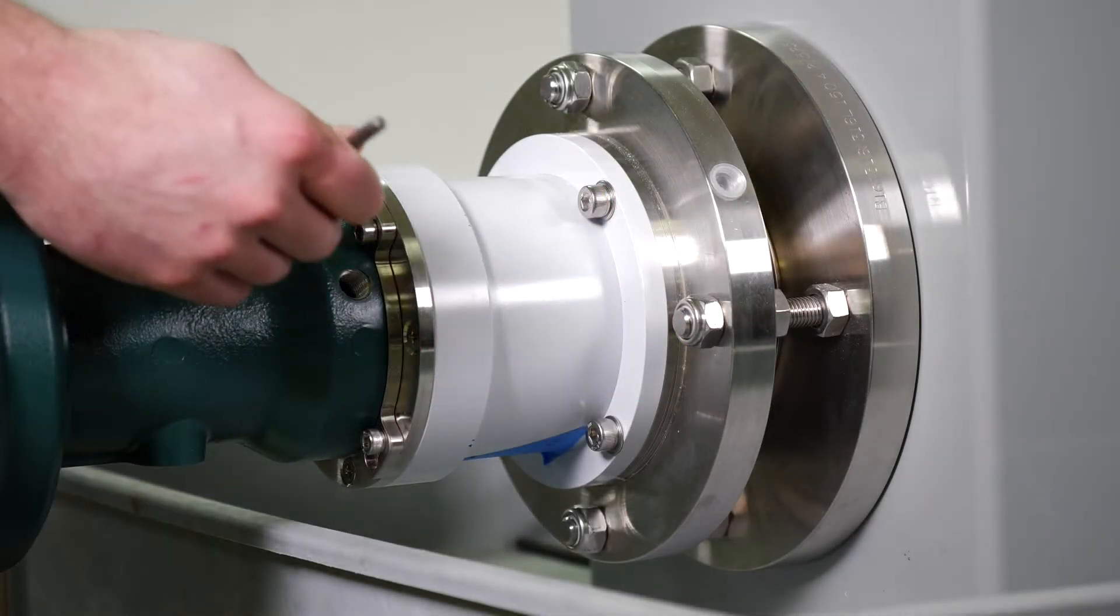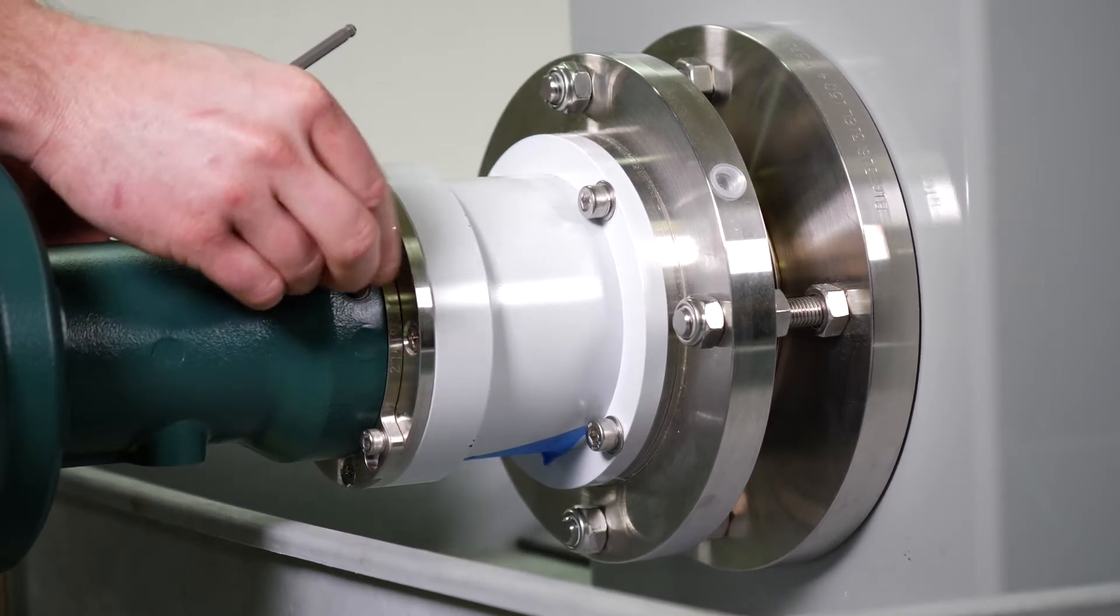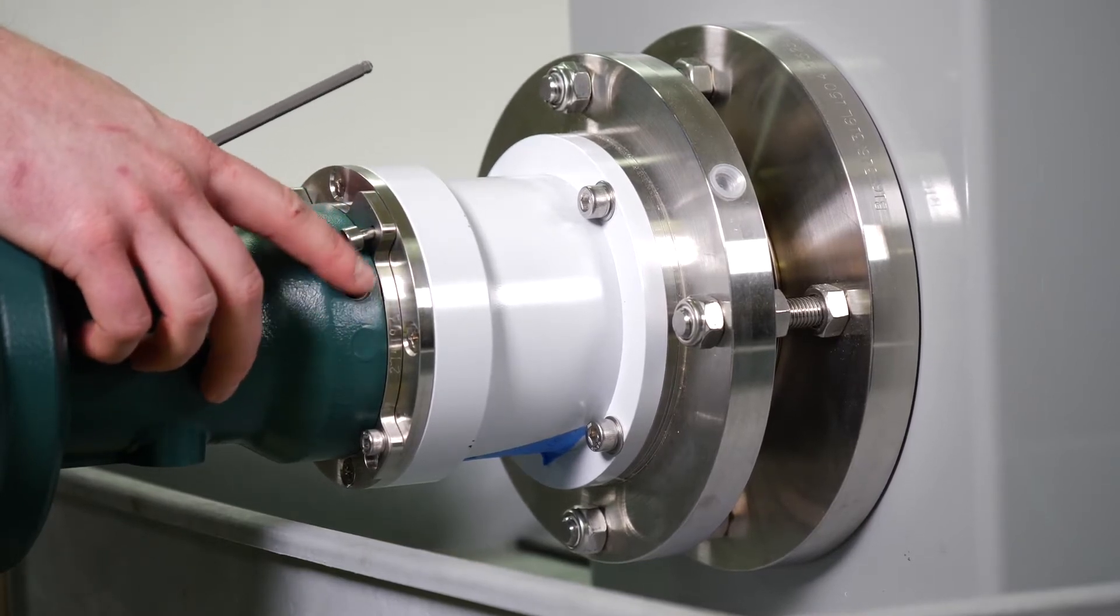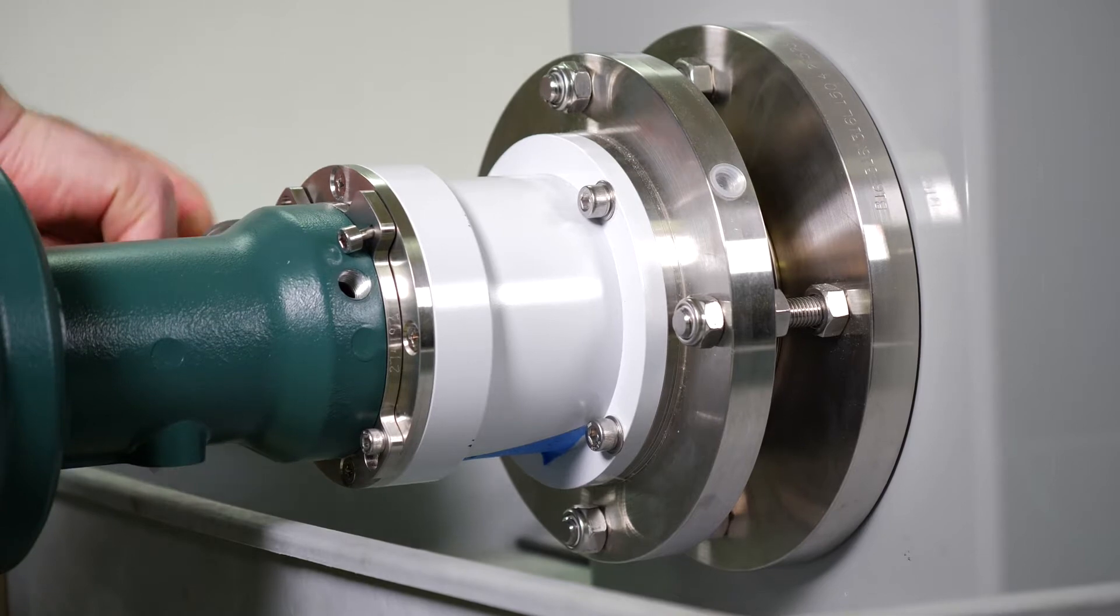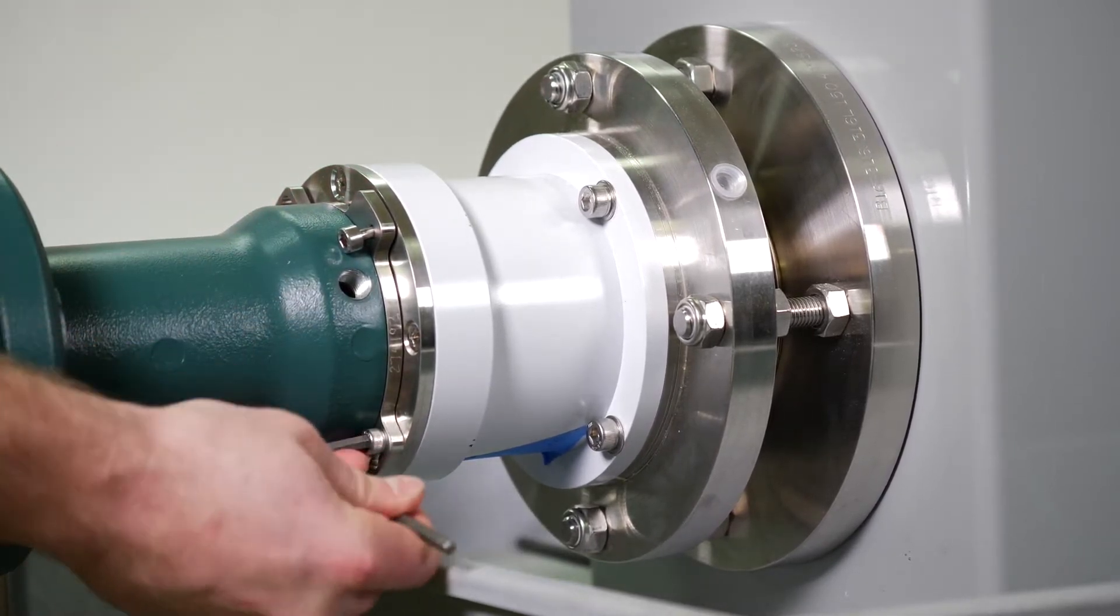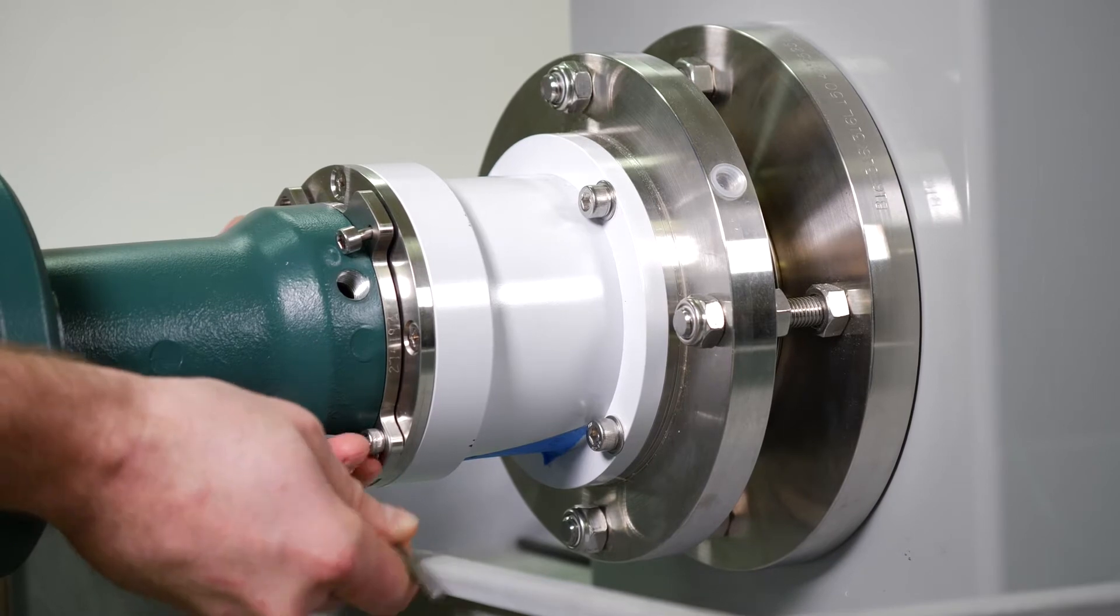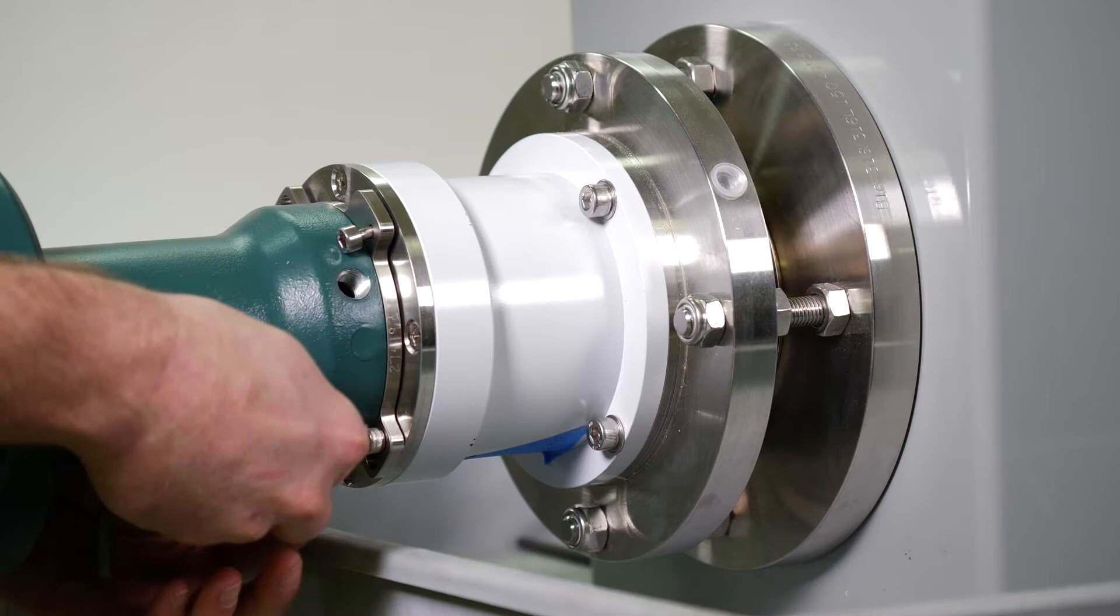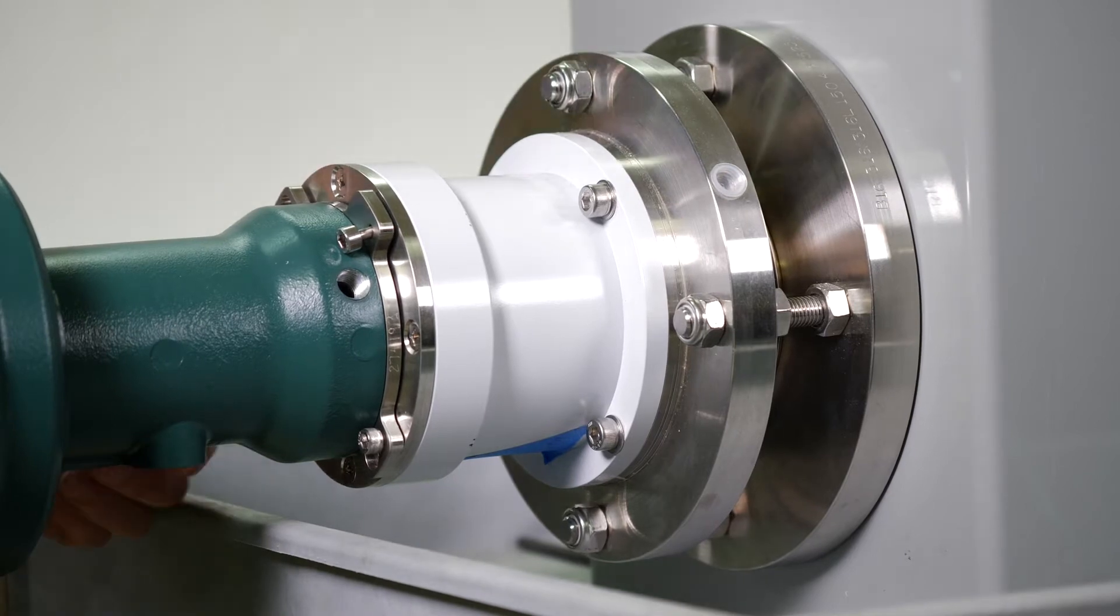Using the M5 Allen wrench, first loosen the captive screw connecting the analyzer to the LAO or large aperture optics assembly. You'll know it's sufficiently loosened when it hangs freely. You don't want to keep loosening it, otherwise it will drop out and you'll lose it and you'll have to replace it. Then remove the remaining three screws a couple of turns. Keep in mind that captive head screw is always on the top right that I've loosened first.